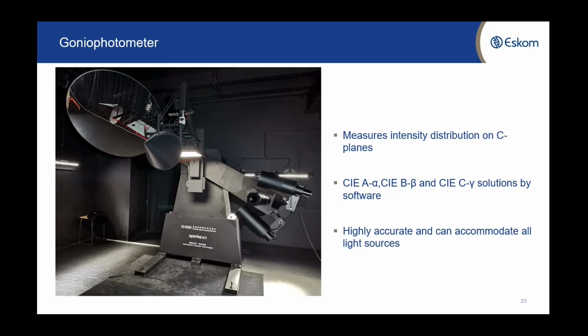Now, in this room, we set it as per standard. The temperature is 25 degrees plus minus 1, and also this room is quite dark. When I say it's dark, I mean it's actually darker than dark. On a full moonlit night, the amount of light that you can see is 0.1 lux. Now, lux is a standardized unit of measurement of light level intensity. As I mentioned, on a full moonlit night it's 0.1 lux, but in this room, it's 0.01 lux.